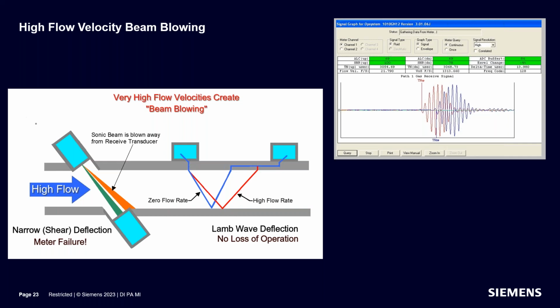It shows the delta time is 13.98 microseconds. The frequency code is 128, and I did the math on this the other day. Frequency code 128 is 250 kilohertz, which means that the period of one cycle is 4 microseconds. And so these beams are shifted by a little over 3 cycles, and there's your 13.99 time difference. So that would be typical of a gas. And many times with gas, the up and down signals would be shifted even further. This is a totally measurable condition right here. 3 cycles of phase shift, only because of Lamb wave. Without Lamb wave, there is no way to do gas flow measurement. It would destroy a shear wave signal altogether.